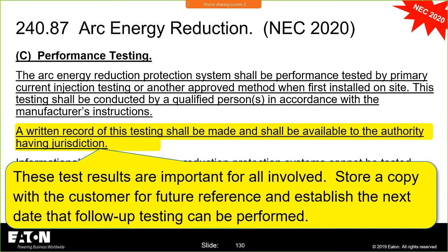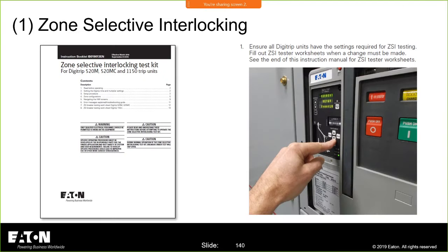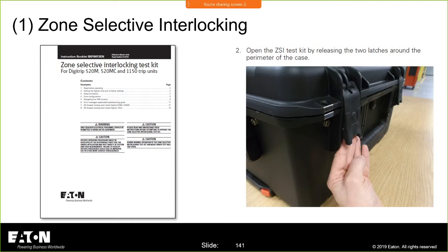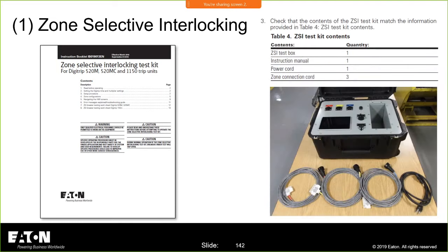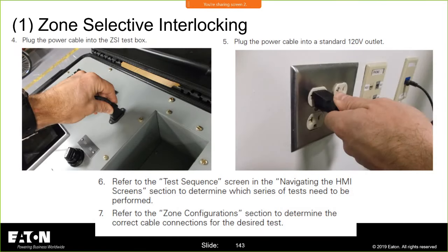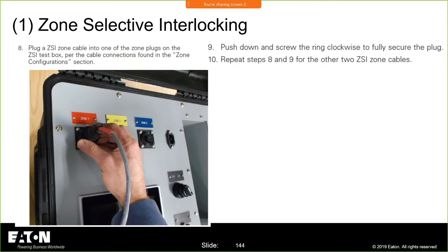And the last thing I'll say is 240.87 also has performance testing. It's just about the same as what you have over in fuses. So going through this is really a regurgitation of exactly what we covered outside of zone selective interlocking, which was not in the fuse section. And for ZSI, we have a whole bunch of, here's the performance testing. Here's a document that we have for zone selective interlocking. I mean, they even show the guy's hand, and they walk through everything. Here's how you open the case. Here's what should be in the case. Here's where, remember to plug it in. Okay. I mean, here's how you have your zone 1s and zone 2s.